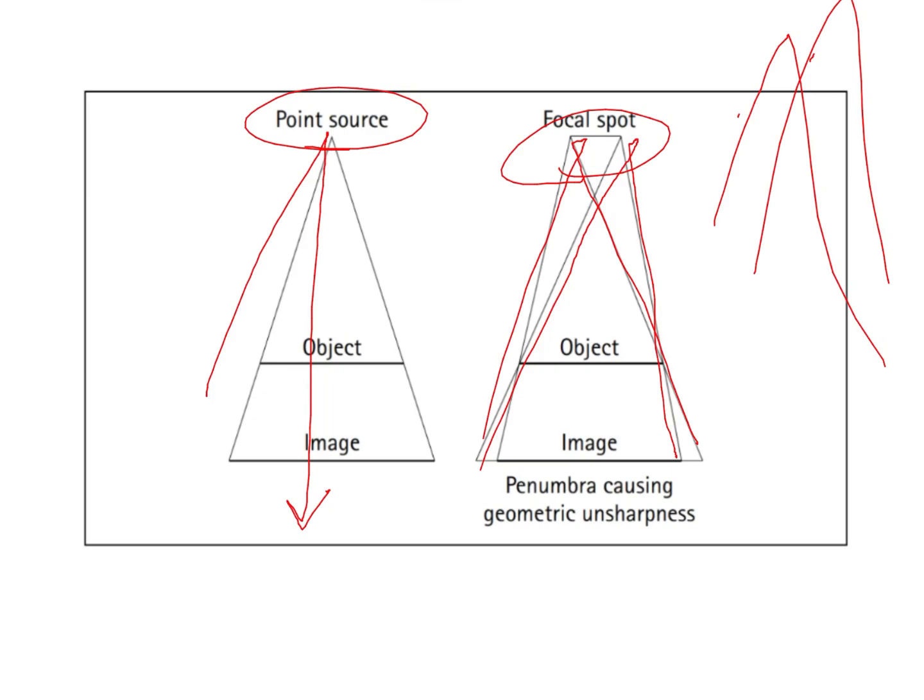Whereas, if you have an effectively small focal spot, all your rays will hit only in that one point and all the rays will have the same direction after being reflected. So, the smaller the focal spot, the sharper the image is going to be.